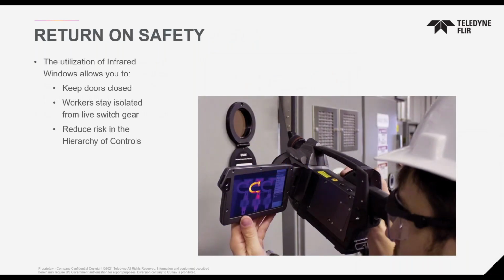With IR windows, you keep the door closed, so workers stay isolated from that live switchgear while still able to perform their inspections, reducing risk in the hierarchy of controls. The hierarchy of controls drives into some of the standards the NFPA set, where you have controls in place over your environment to ensure safety for those performing tasks and operations. So to improve safety, we focus on keeping doors closed and keeping high voltage isolated from our inspectors.